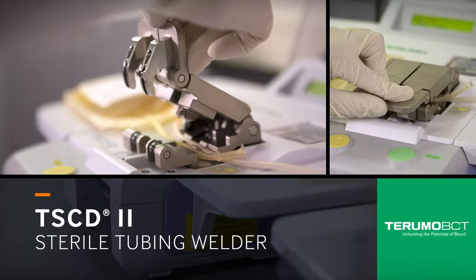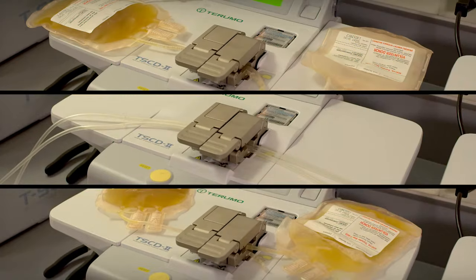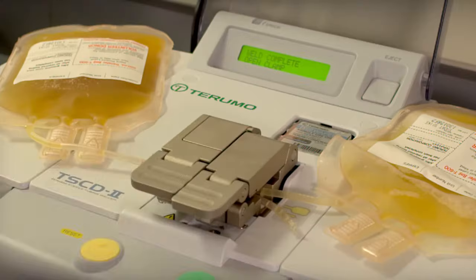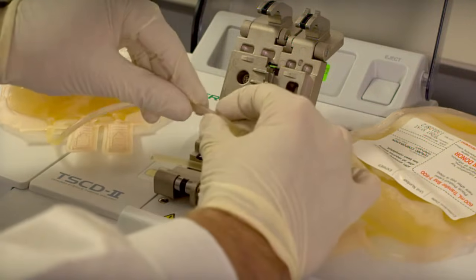Professionals who need reliable seals look to the TSCD-II sterile tubing welder. The TSCD-II welder gives you the versatility to create a tubing seal that's wet to dry, dry to dry, or wet to wet without changing any settings. This single device can weld any combination of polyvinyl chloride tubing connections you need.